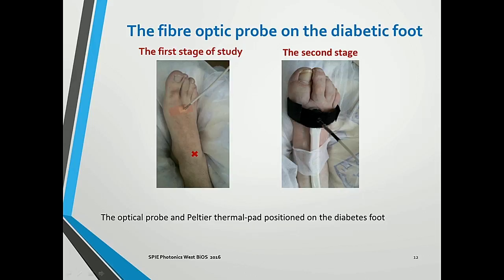So this is a probe. We measure 2 positions between 2 toes. And here, actually, the clinician wants this one. They palpate here, looking for the pulse because of the big artery. So we compare the two. This is how the temperature test looks on a foot. It's quite big. This is a Peltier element with water. Unfortunately, we have to keep water cooling because a usual radiator is not enough. Otherwise, it will be too big, and it's not useful for the patient.